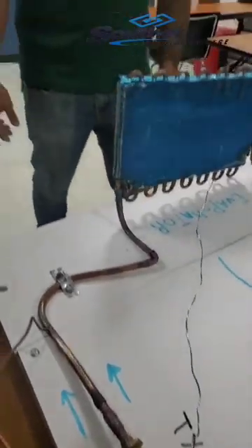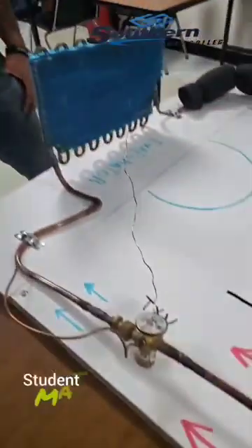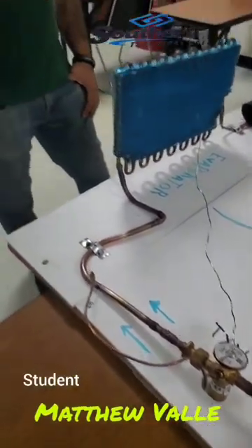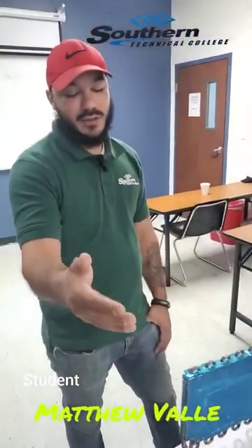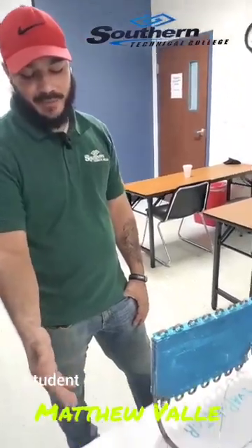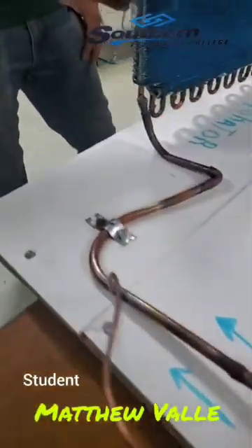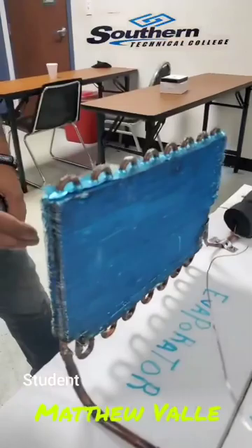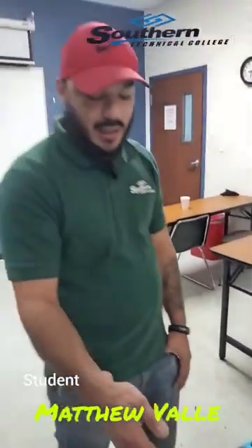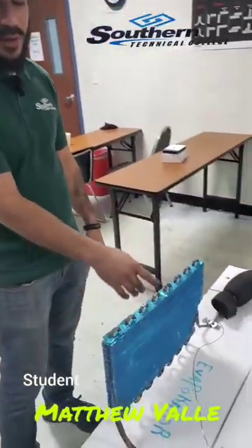Thank you, Ian. After Ian just expressed, after the TXV, you have a 75 and 25 ratio. 75 liquid, 25 gas. What's happening after that, it's coming into the evaporator coil at a low pressure, low temperature, saturated liquid and gas going through the evaporator.